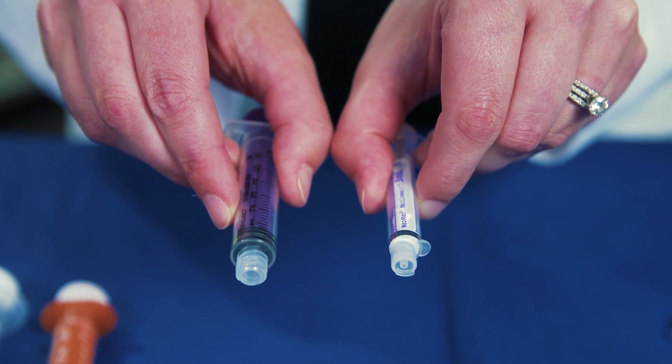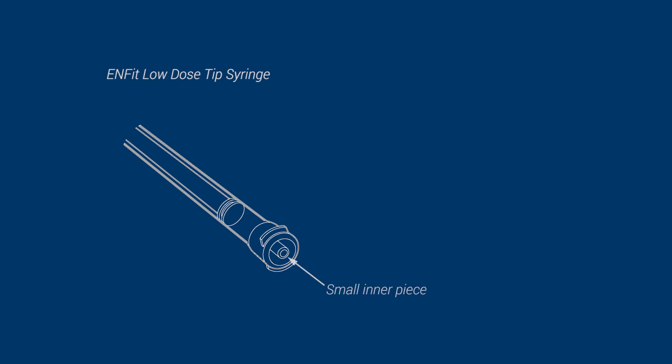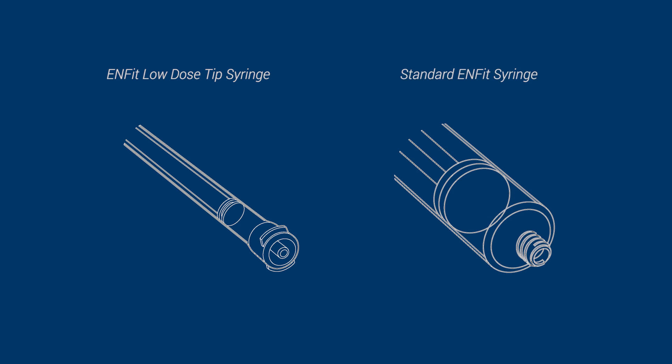ENFit tip syringes may look different depending on the manufacturer, but are all compatible with the ENFit system. There are two primary differences between smaller and larger ENFit tip syringes. The smaller size should have a low dose tip, which includes a small inner piece added to the tip of the syringe, and the larger sizes will have the standard ENFit tip. The low dose tip was developed to address clinicians' concerns about dosing accuracy when delivering small medication volumes.